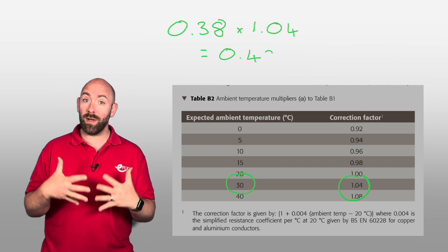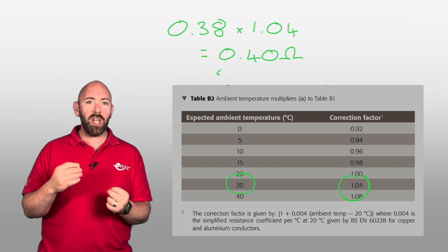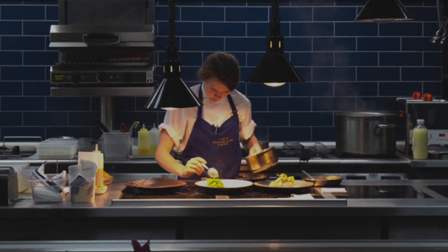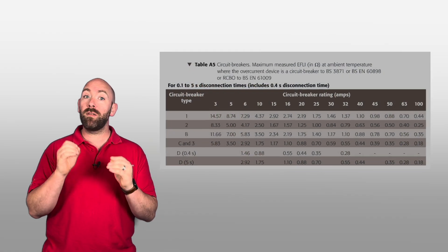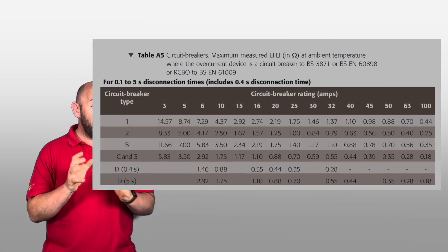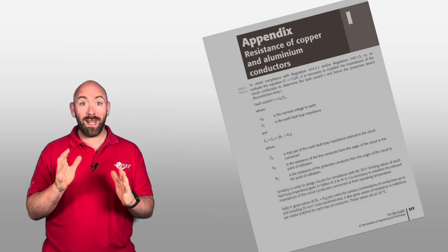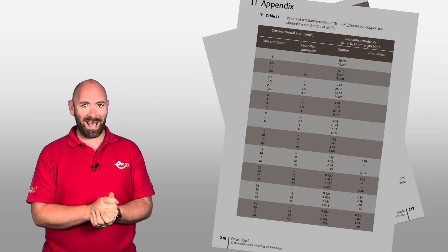The higher temperature increases the resistance. In reality this could mean that a circuit installed in an area where the ambient temperature exceeds 20 degrees — when combined with another test (look out for a future video on that) — may exceed the maximum permitted values for our circuits. These values are also given in the on-site guide in Appendix I if you don't have your Guidance Note to hand.